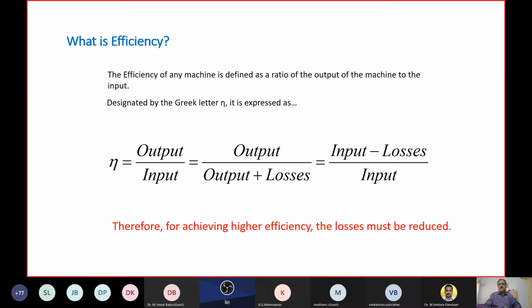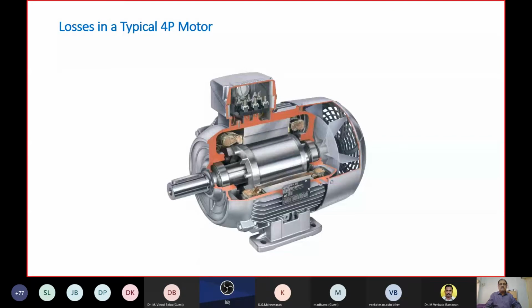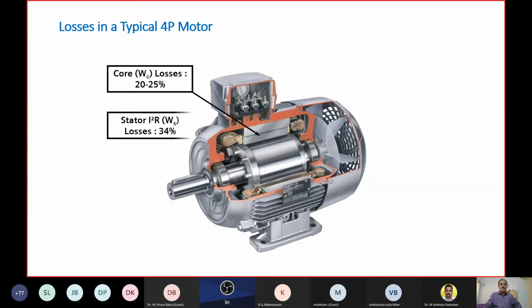There is no tinkering with the output of the motor. Output is a standard. For example, if you have an 11 kilowatt or a 15 kilowatt or a 22 kilowatt motor, that is never disturbed, that is never discussed. What is happening is the reduction in the input through the reduction in losses. Therefore, energy efficiency in a motor is achieving reduction in losses so as to improve the overall energy efficiency of the motor.